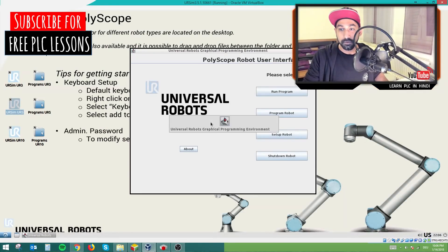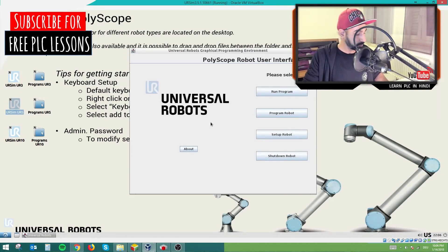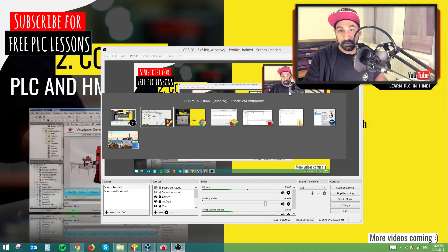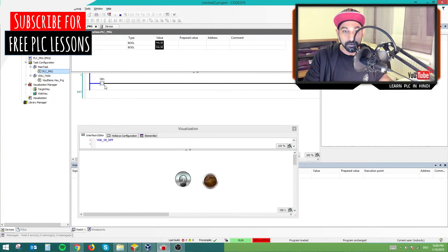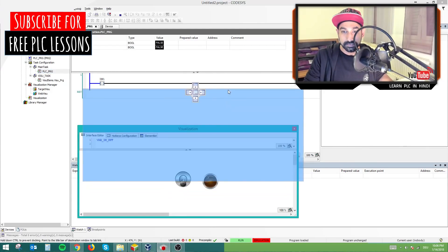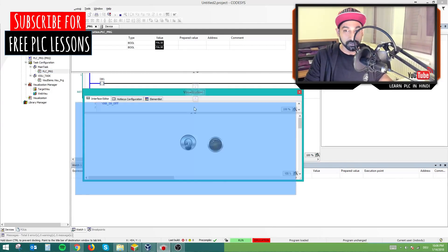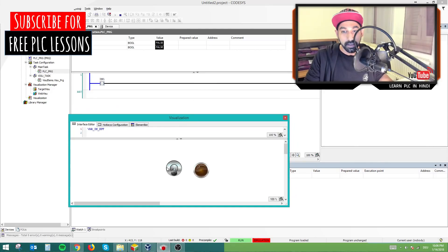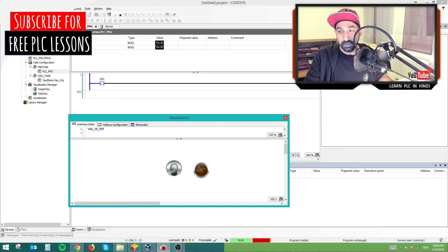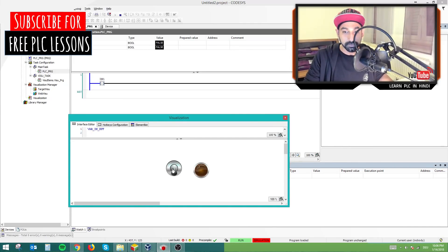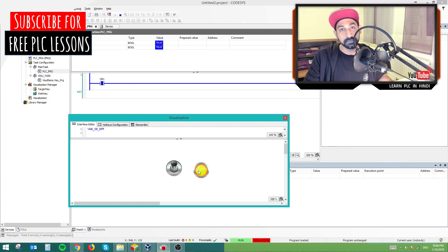Let me show you one example. This is my Codesys. This is a small ladder logic with one input and one output. This is the HMI screen, it says visualization. This is my switch and that's my output. My switch is linked to my input bit, my output is linked to my output coil. This is an indicator. If I turn on my input, this bit goes on, the logic is solved, and output is on.